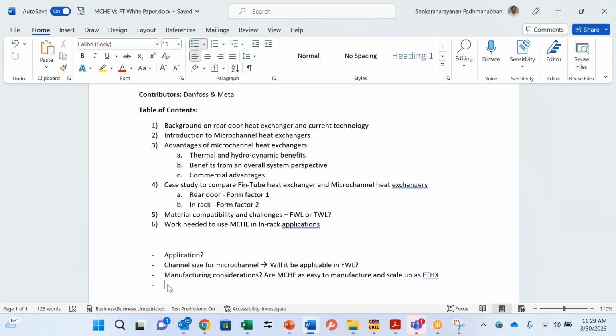It actually decreases the fan power, because the microchannel has a much more streamlined hydrodynamic performance. So for a given capacity and heat transfer, there are three variables here: capacity, fan power, and airflow. If you have the same fan power, you get more airflow through the microchannel compared to a fin and tube. And if you want to keep the same airflow, you can drop the fan power, because the air-side pressure drop on a microchannel is smaller compared to a fin and tube of the same capacity.